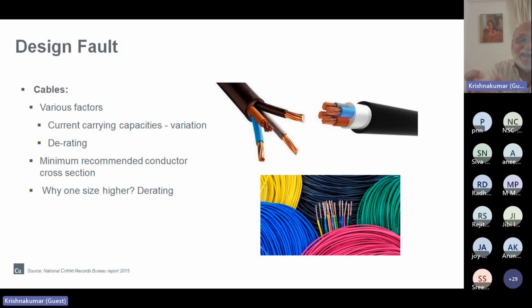So there is a time gap of milliseconds. That time gap is quite good enough to heat up the copper conductors in your wires and raise the temperature beyond 100 degrees. Why 100 degrees is important is that most of the insulation, which is PVC, will melt or catch fire at about 90 degrees centigrade. That will play havoc.